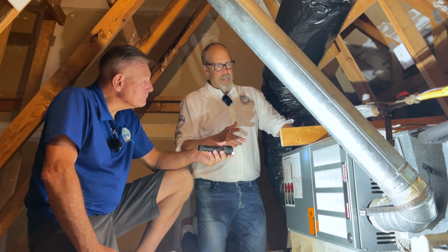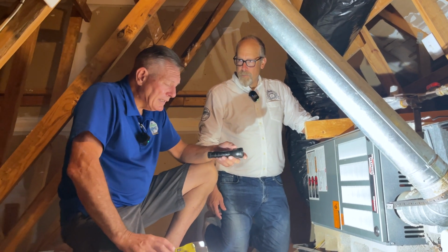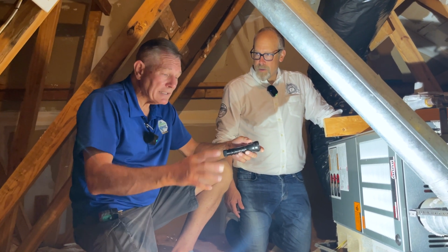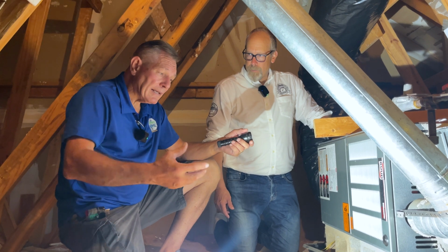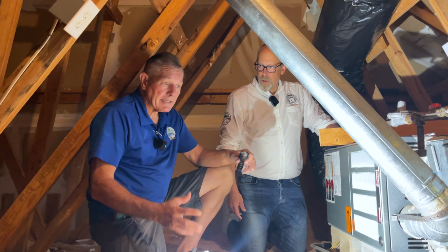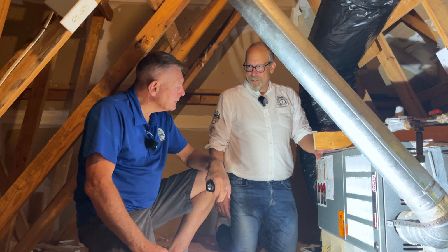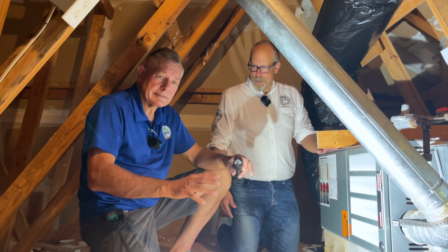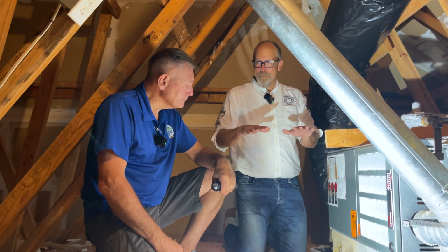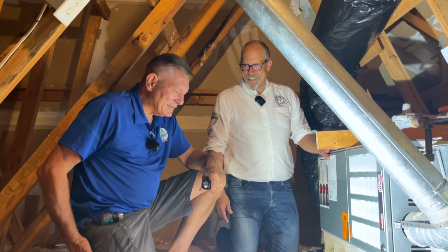And speaking of return and supply, downstairs you're going to do Delta T? Delta T. What is that? That's checking the heating and air conditioning. The heat and the cold have a different degree of temperature change, they call it Delta T. The temperature being supplied to the house versus the temperature exiting, returning. We check both of those, and there should be a difference. The deviance in air conditioning is, I think, 14 degrees. That's what you want to check, to see how close we are to that, again, the efficiency of the system. And if it's the same, that's no good. That means it's not cooling off or heating. Yeah, that means open the yellow pages.